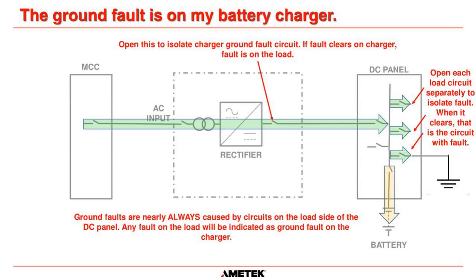If you really think that it's in the charger, the easiest way to confirm if the ground fault is in the charger is by opening this disconnect here. Okay? That takes away all of the load circuits from the charger. So if you open the output breaker on a charger and the ground fault light stays on, then yes, there is a problem in your charger and the ground fault is in there. But that is highly unlikely.